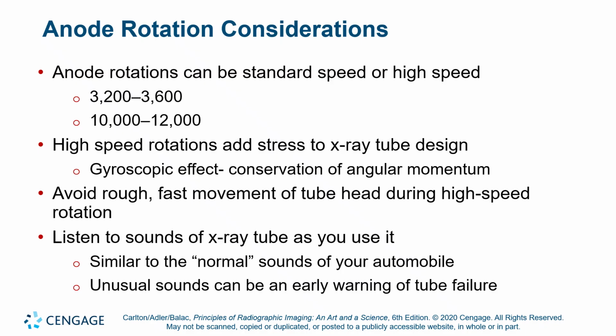So typically they come in two versions: standard speed, which is a little bit over 3,000 RPMs, and then high speed, that's 10,000 to 12,000 RPMs. High speed rotors typically have to be bulkier and have more mass and thicker anode stems, because you do get a gyroscopic effect and a conservation of angular momentum, and they have to be machined and precisely engineered so there is no precession, no wobble in the rotation.